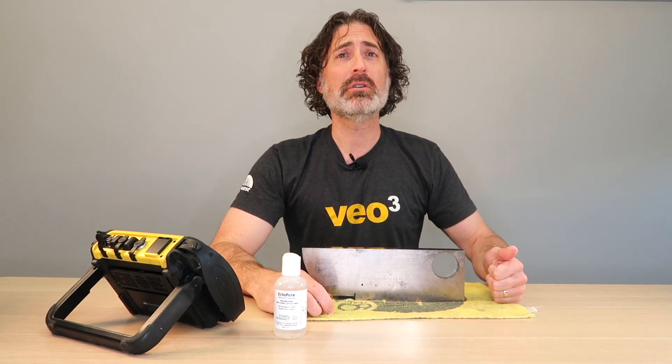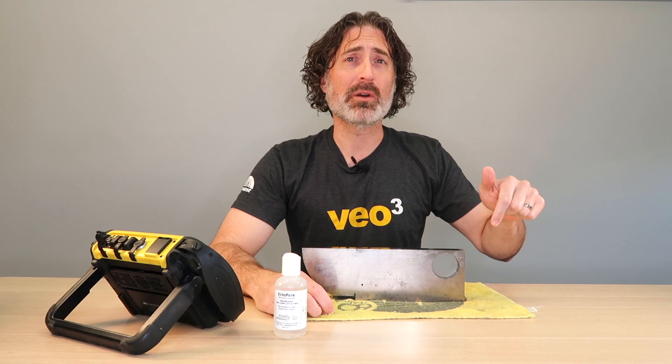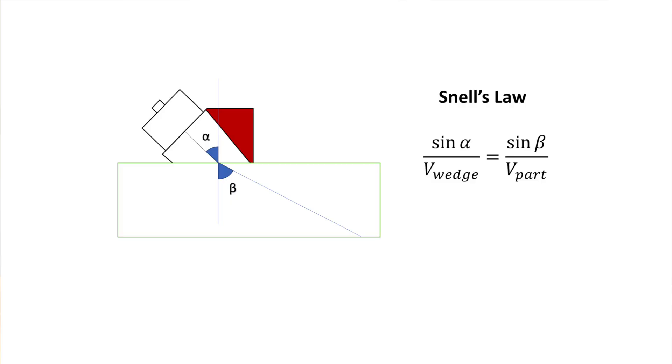If I increase the temperature, my angle is going to go up. If I decrease the temperature, it's going to go down. Let's start with a basic setup. We've got a transducer and wedge on a piece of steel and we're going to use Snell's law. This is the equation that you learned in your UT Level 1 course, and it defines the relationship between the velocities of the wedge and the steel and the angle of incidence and refraction.